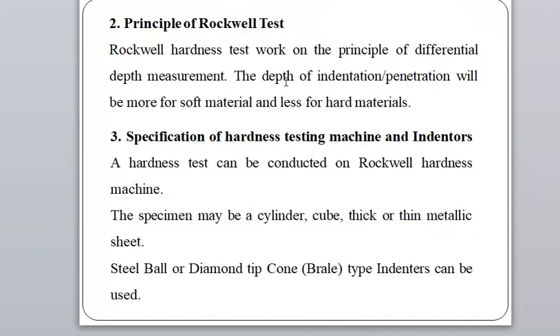The principle of the Rockwell Hardness Test is based on differential depth measurement. The depth of indentation or penetration will be more for soft material and less for hard material. The depth of penetration of the indenter into the sample is used for calculation of the hardness value.